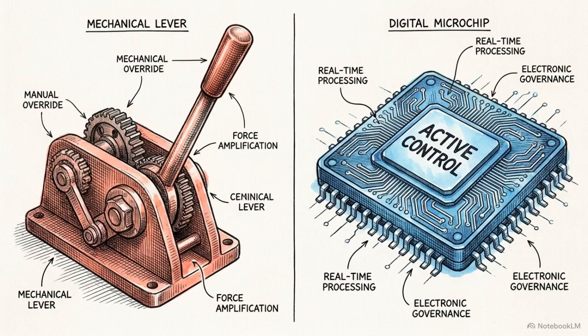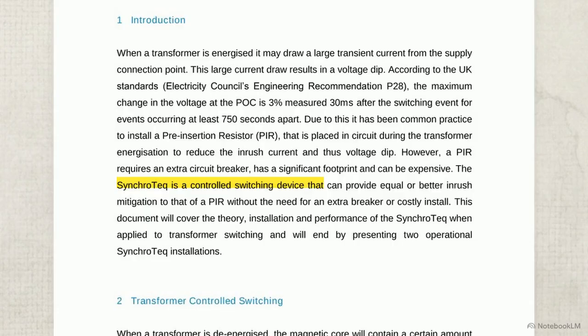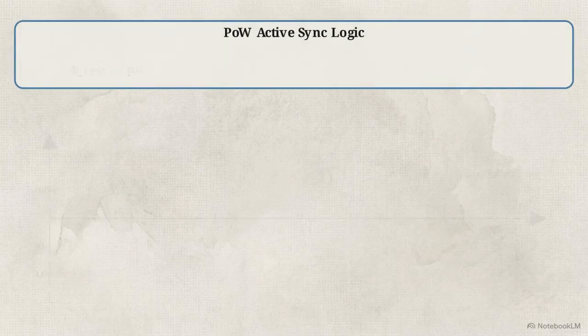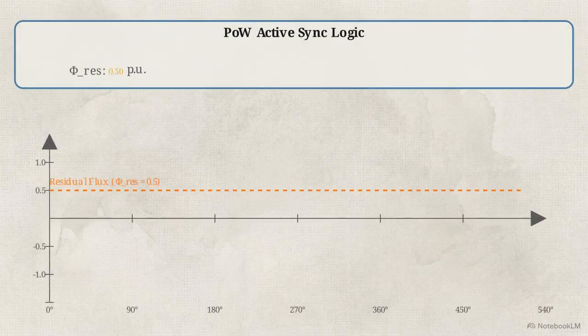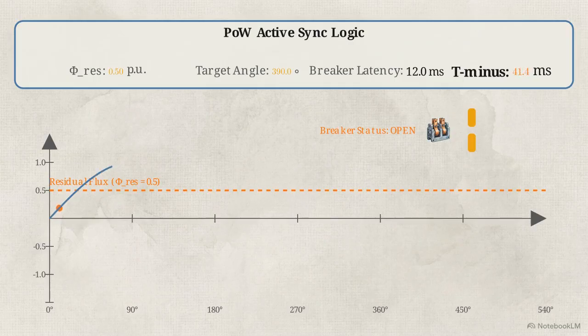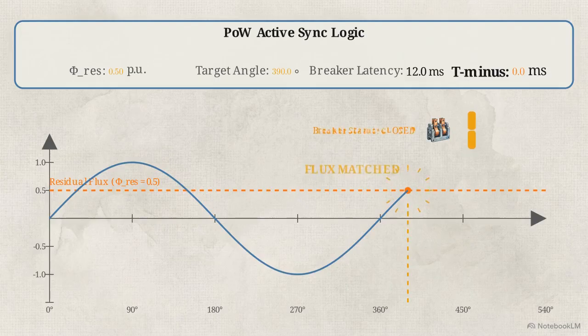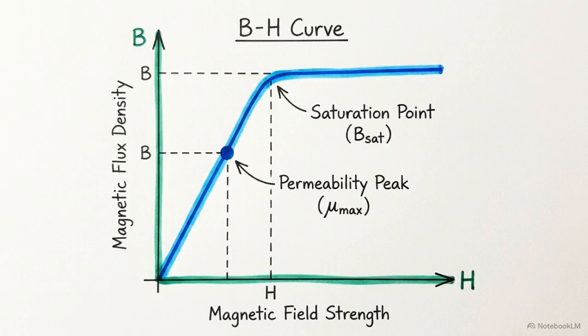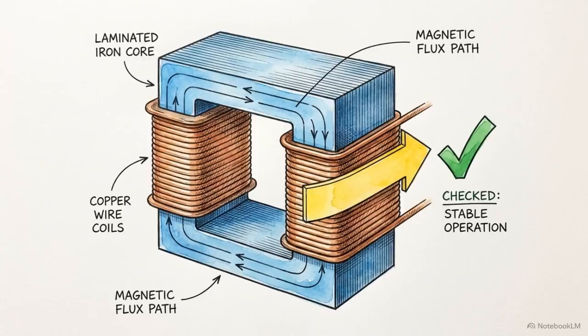Bypassing this bottleneck requires abandoning passive switching in favor of active precision mitigation hardware. This technical document introduces one of the most effective solutions, point-on-wave, or POW, switching controllers. A POW controller actively monitors the voltage at the time of de-energization to calculate the exact residual flux left in the core. When it's time to reconnect, the controller waits for the precise millisecond on the voltage wave that will match the prospective flux to the residual flux. By matching the magnetic states, the controller prevents the total flux from breaching the knee of the BH curve. The core never enters saturation, and the inrush current is neutralized.